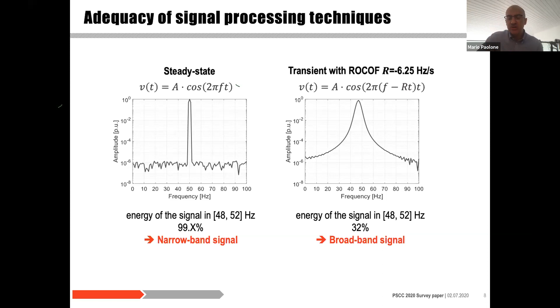Instead, if you do a Fourier analysis of a signal experiencing a ROCOF like the one in South Australia, with a negative ramp rate of 6.25 hertz per second, you see something interesting. The spectrum is no longer narrow, in the sense that it's pretty continuous and spread over a relatively big frequency range. If you look at the typical frequency interval where we study power systems, a power system at 50 hertz rated frequency, with the energy of the spectrum concentrated between 48 and 52 hertz, you realize that only 32% of the energy of that signal is concentrated in that band. Then you may ask yourself whether a phasor approximation is good enough to represent this kind of phenomenon.